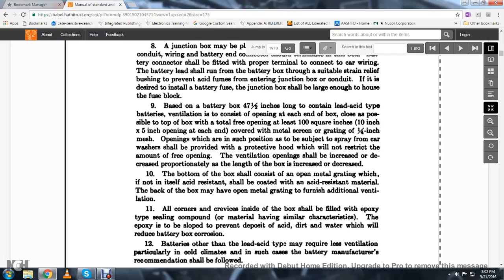If it is desired to install a battery fuse, the junction box should be large enough to house the fuse box. Based on battery box 47.5 inches long containing lead acid type batteries, ventilation consists of openings at the end of the box, with a total free opening of at least 100 square inches, or a 10-inch by 5-inch opening at each end, covered with metal screen and grating of quarter-inch mesh. Openings subject to spray from car washers shall be provided with a protective hood that will not restrict the free ventilation opening.